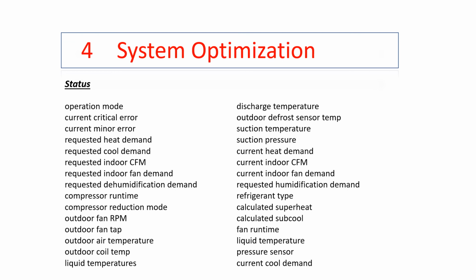The very last thing in section 4, system optimization, is our status. We discussed this earlier. This will show what our outdoor fan RPM, air temperature, coil temperatures, liquid line temperatures, or indoor fan. It also shows a requested demand and an actual demand. So you'll see we might be requesting 100, the unit might be running at 75%. This will let us know if we have an issue with a defrost sensor. This will show us what operation mode we're in.